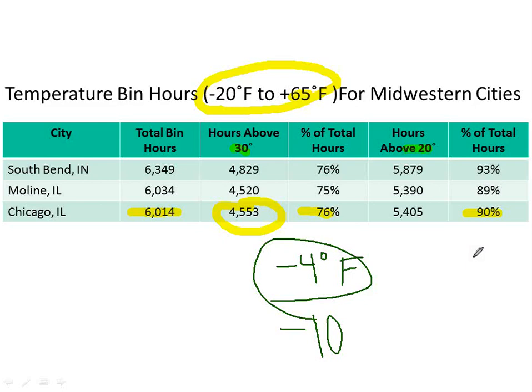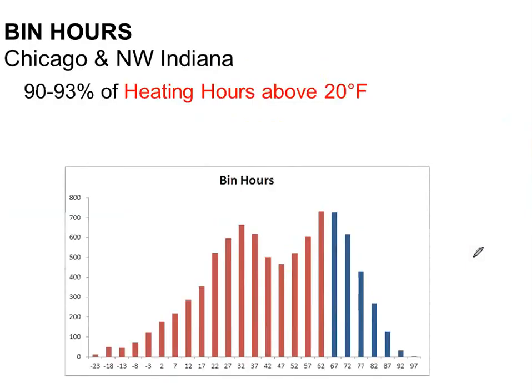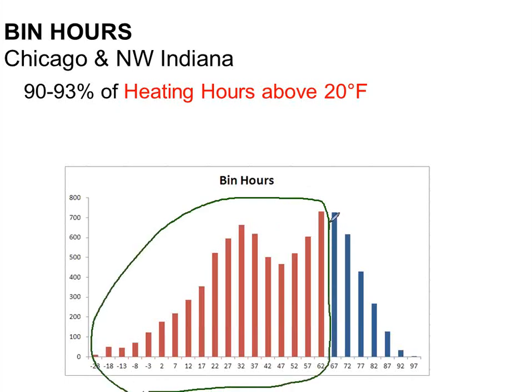If I got a fully modulating unit, I can pretty much give you the amount of BTUs you need at any given time throughout the day. And just for point of reference, all these red hours here, those are heating in Chicago area. So below 65 degrees heating, all these hours added together, this little bit of blue is cooling. A lot of us have gotten really good about talking about SEER and air conditioning efficiency, but it's kind of irrelevant when you think about heating efficiency. Heating gas is cheap, but nonetheless, it still does cost money, and it costs way more than cooling buildings does.